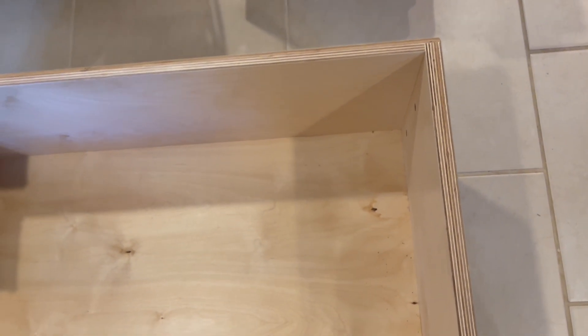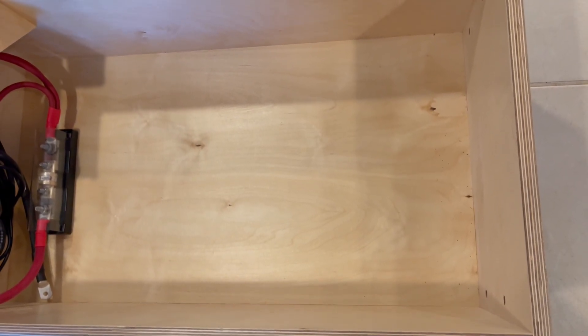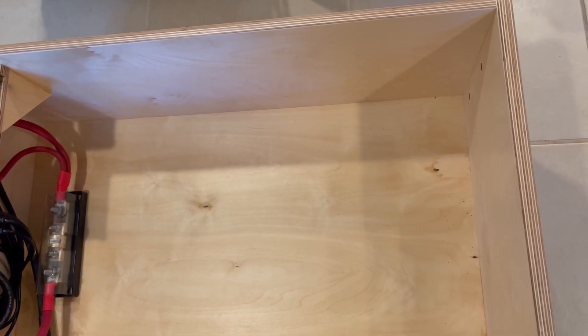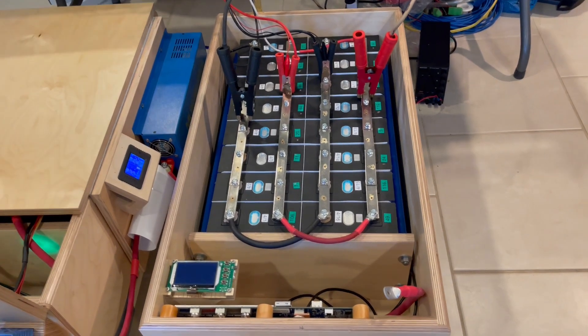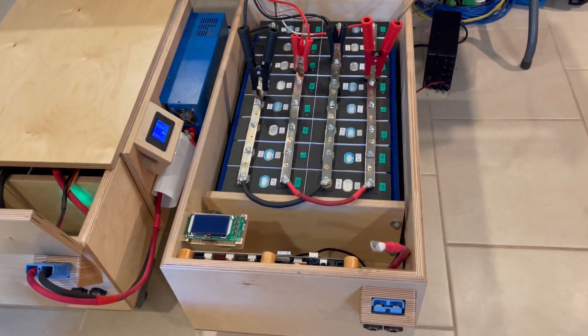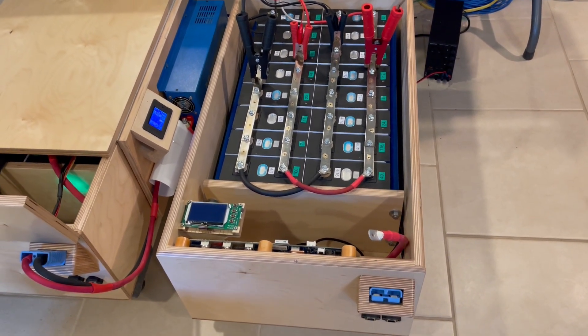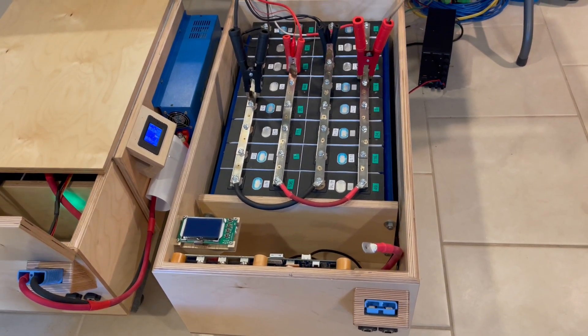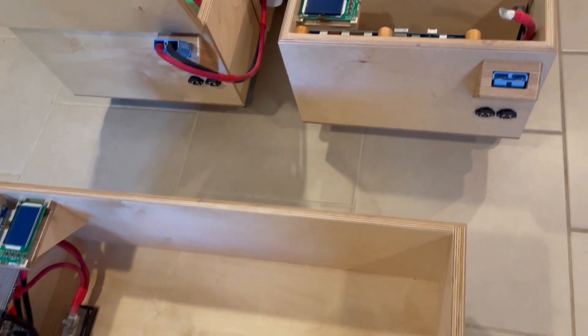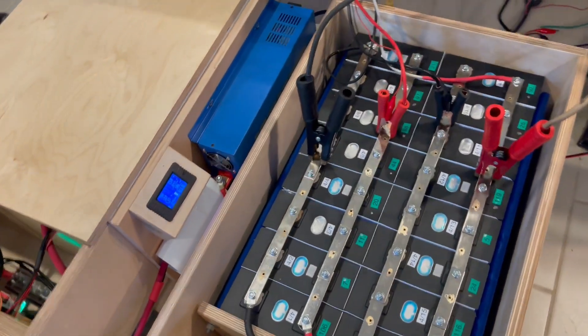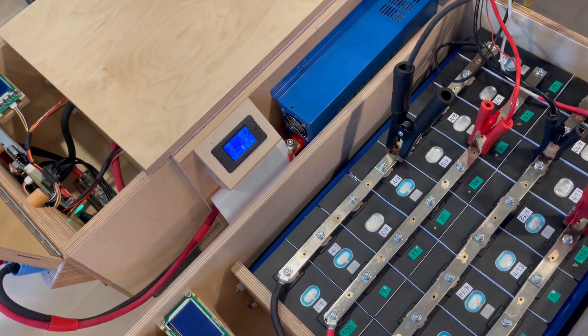This morning, I'll go ahead and put the rods in, and I'll get the next group of cells installed so that it looks like this and is ready to go when it's time for this battery to be capacity tested and dump its energy into this one. And we'll just leapfrog down the line until we've done all 16 batteries.